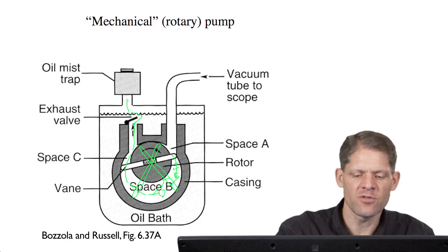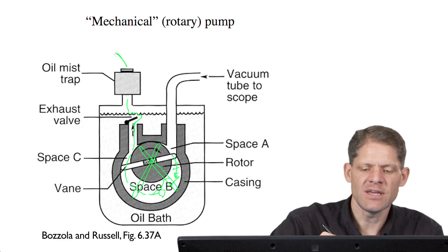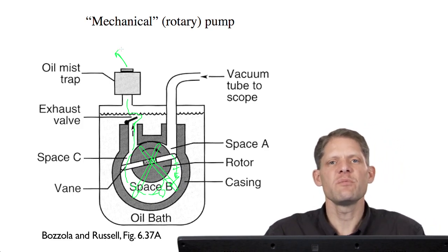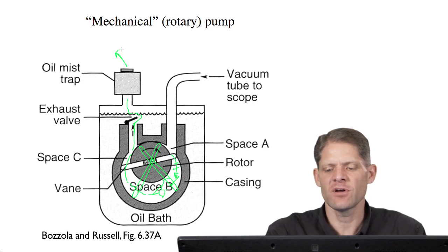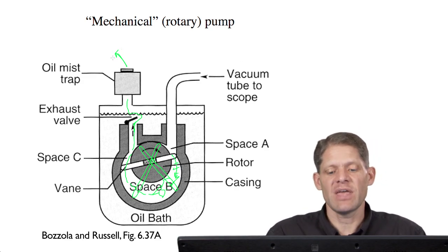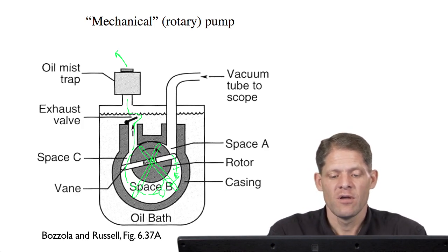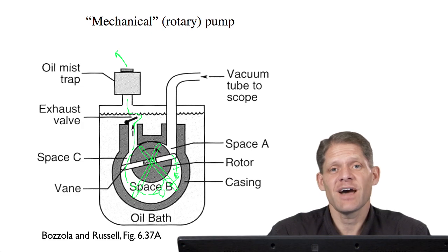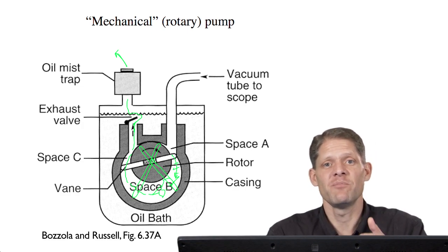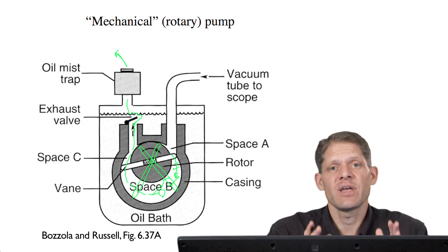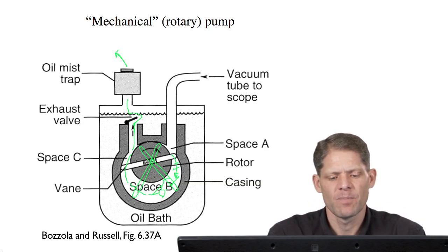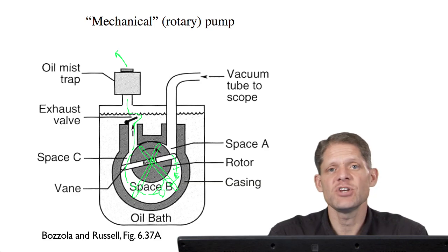And from the exhaust valve, they go through an oil mist trap and are expelled into the room. So the mechanical rotary pump just gradually scoops gases out of the column and puts them into the room. Now mechanical pumps create vibrations. They're easy to hear in the room. And so it's important not to be taking your very best highest resolution images while the mechanical pump is on. Instead, one waits until the mechanical pump is off and then you take your picture. Mechanical pumps also require some maintenance. You have to change the oil every once in a while.